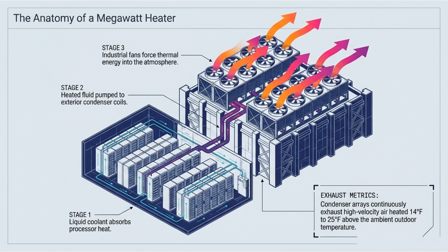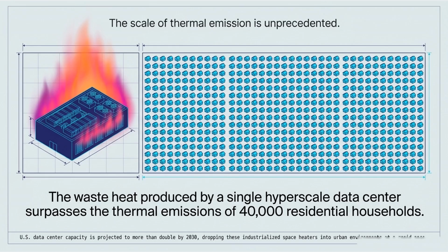The result is this continuous high-velocity blast of heated air that is expelled directly into the surrounding environment. We aren't talking about a slight warm draft here. The air these arrays exhaust is typically 14 to 25 degrees Fahrenheit hotter than the ambient outdoor temperature. So if a facility is operating in a region where it's already an 80-degree summer day, those fans are continuously pumping out millions of cubic feet of air that is well over 100 degrees. And that volume is key - the waste heat generated by just one single hyperscale data center can easily surpass the combined thermal emissions of 40,000 residential households. From just one building. That is insane.